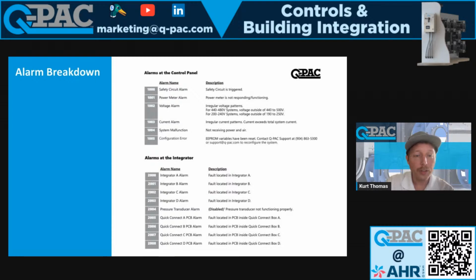If you do have a voltage alarm, then you have something wrong, likely with the voltage. Maybe you have super low voltage or super high voltage. If you have a 460 volt system or 480 volt system, anything below 440 is going to throw an alarm. Anything above 500 is going to throw an alarm. And then for a 200 to 240 volt system, anything below 190 and anything above 250 volt is going to throw an alarm.